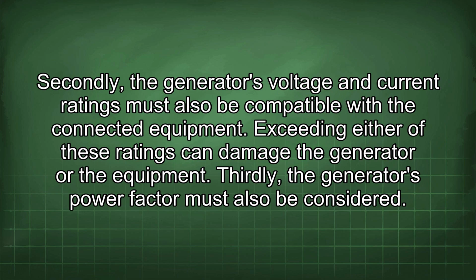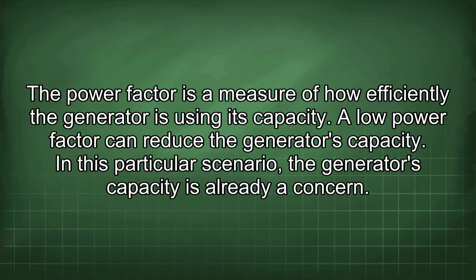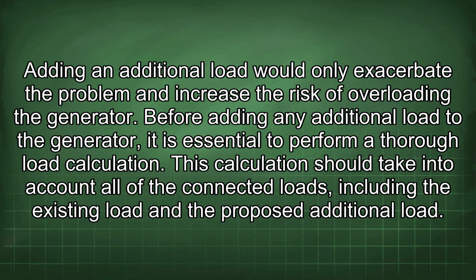Thirdly, the generator's power factor must also be considered. The power factor is a measure of how efficiently the generator is using its capacity. A low power factor can reduce the generator's capacity. In this particular scenario, the generator's capacity is already a concern. Adding an additional load would only exacerbate the problem and increase the risk of overloading the generator.